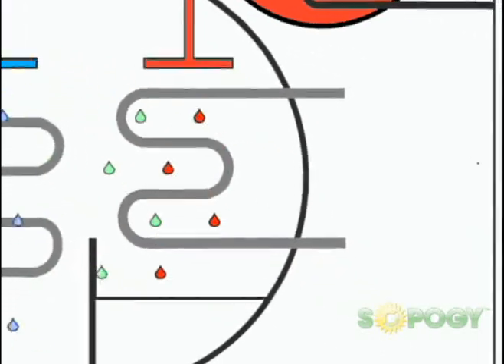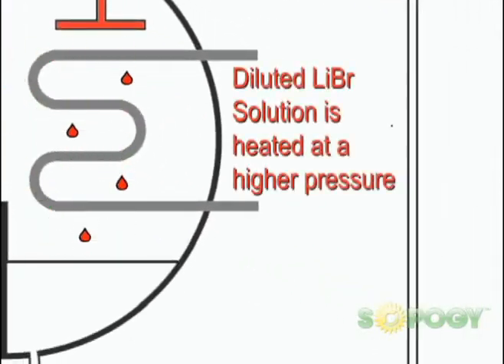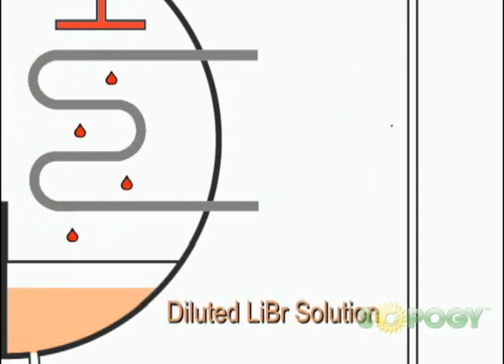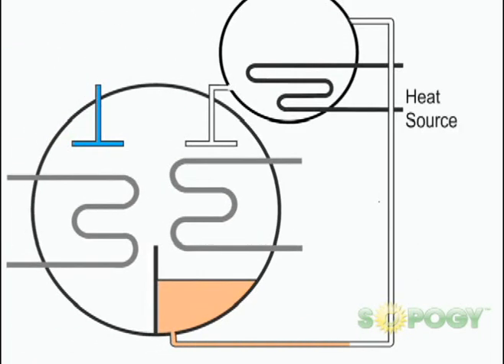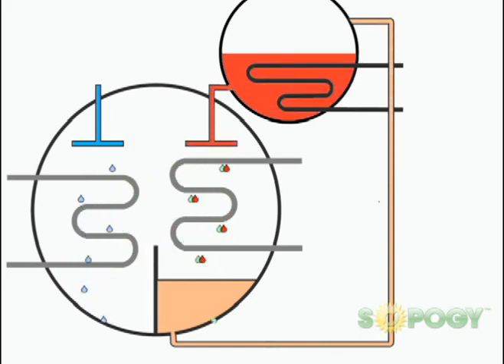The diluted solution, which contains the absorbed refrigerant vapor, is heated at a higher pressure. As lithium bromide becomes dilute, it loses its capacity to absorb water vapor. It therefore needs to be re-concentrated using a heat source. This leads to the vaporization of the refrigerant, and thus the solution is restored to its original concentration. The cycle keeps repeating itself to give the desired chilling effect.